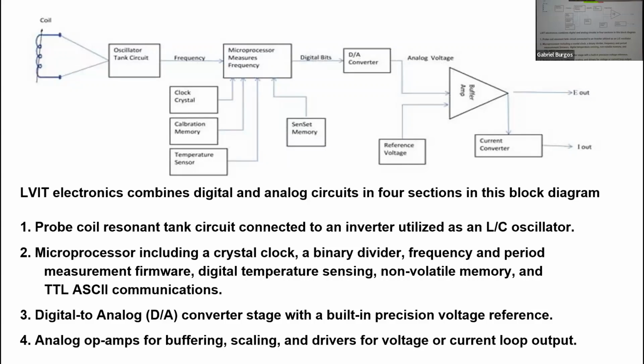Here, what happens is that frequency change, because it's a square root function, is not linear. So what you do is put it into the processor, and then you have a calibration memory with a lookup table that straightens it out for your purposes.